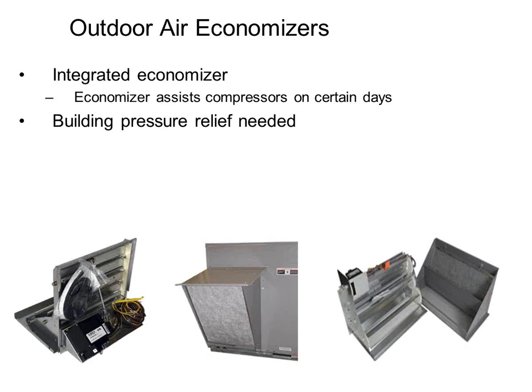I also have to think about pressure in the building. If I'm going to open this damper and suck a lot more outside air in, where is that air going to go? Whatever I suck into a building has to have a way to get out of the building, right? No choice at that. Whatever goes in has to come out.